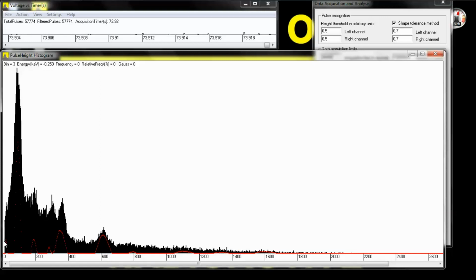And if we were to give this a little bit more time, it would actually increase and become even stronger. We might actually want to lower the height threshold in arbitrary units for a spectrum like this, because a lot of these gammas are going to be coming in at the same time and bumping into one another. Well, they don't actually hit each other, but what happens is they produce photons at the same time. You get all kinds of little sum peaks and everything like that. And changing this number to a lower number, meaning that we need to keep everything much more uniform, is probably going to result in a better shape overall, a better spectrum. But as you can see, it's coming out pretty well.